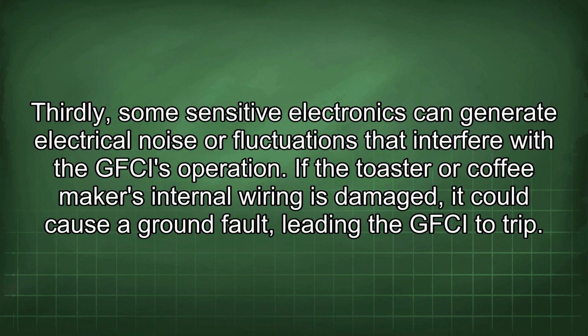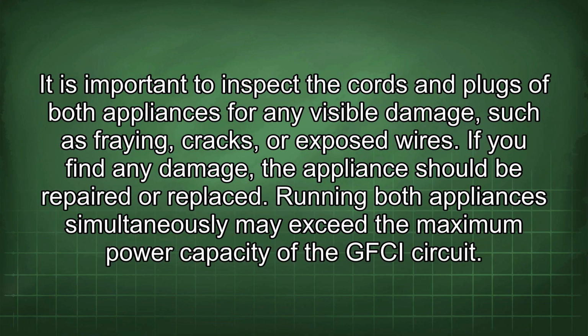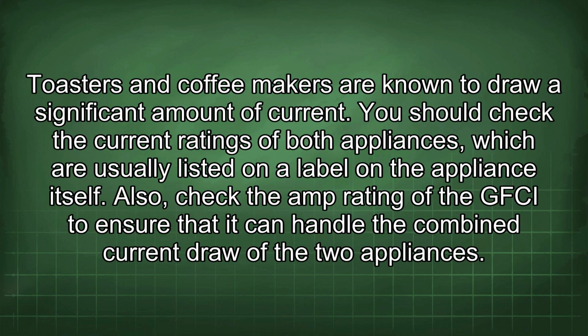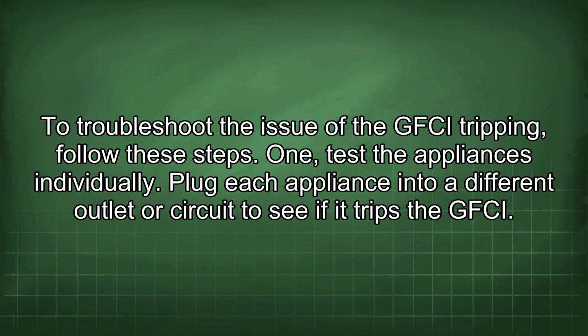If the toaster or coffee maker's internal wiring is damaged, it could cause a ground fault, leading the GFCI to trip. It is important to inspect the cords and plugs of both appliances for any visible damage, such as fraying, cracks, or exposed wires. If you find any damage, the appliance should be repaired or replaced. Running both appliances simultaneously may exceed the maximum power capacity of the GFCI circuit. Toasters and coffee makers are known to draw a significant amount of current. You should check the current ratings of both appliances, which are usually listed on a label on the appliance itself. Also, check the amp rating of the GFCI to ensure that it can handle the combined current draw of the two appliances.